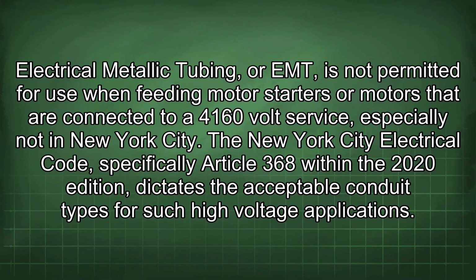Electrical metallic tubing, or EMT, is not permitted for use when feeding motor starters or motors that are connected to a 4160 volt service, especially not in New York City.